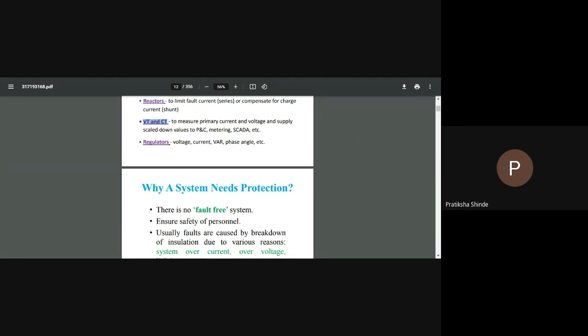For example, the rating of a current transformer might be 100 to 5, meaning the primary current is 100 and the secondary current is 5. Whenever a lightning surge occurs on the primary line, the 100 current is increased up to 200, suppose. So proportionally the secondary current also increases, from 5 up to 10. That increasing current is taken into consideration, and the current transformer gives a signal, or your relay senses the increasing current within a millisecond.